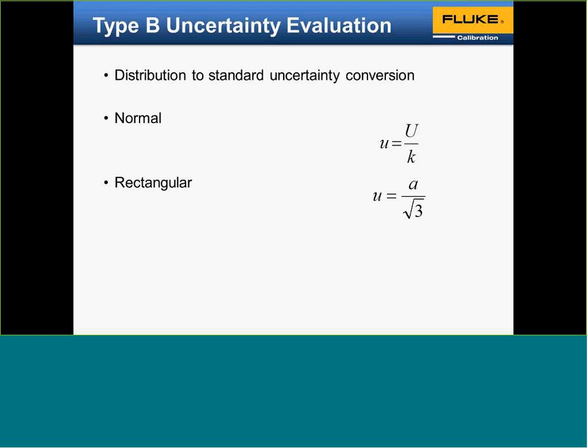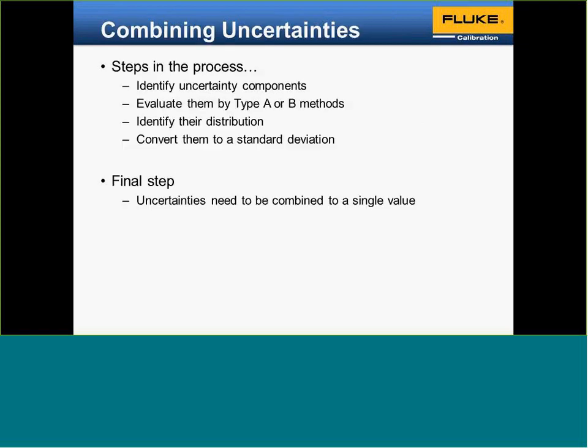Now, if you want a standard uncertainty, there's a divisor for each. For a calibration certificate, you divide by the coverage factor noted on the report. The typical divisor for a rectangular distribution is the square root of 3, which is 1.73.